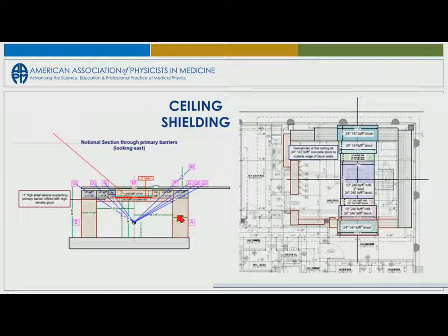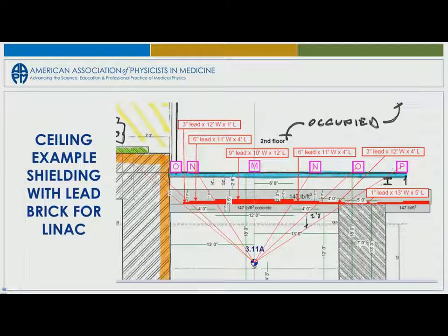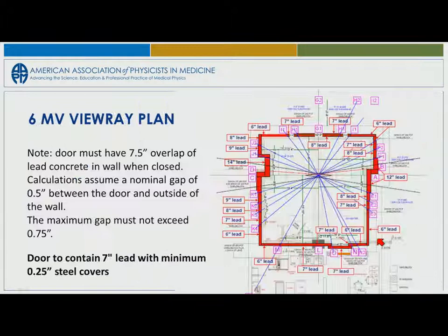So this is what I typically will give the contractors, the primary thickness in the center, and then space it out, feather it out, because you don't want to buy more lead than you have to. So as you go off center, you can go down in your extra thickness of your lead. This is an example that we did with a lead brick, and I call it feathering. So in other words, you start thin, you add the lead as most you need it, you feather it out, and this was obviously an adjacent vault. This was a section with 3 vaults in a row. So you feathered it up, you feathered it down, and then you feathered it up again. And so again, we'll do that usually in 6 or 12 inch increments, because these lead bricks are 6-inch bricks. And so you can add it up to that point.